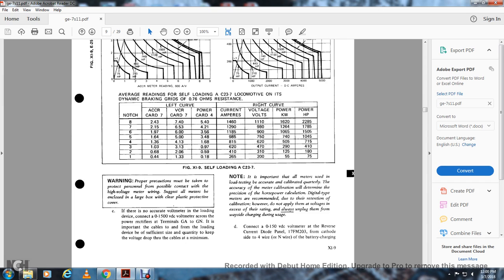This is an important cable to size with sufficient quantity from the loading of the device, to keep the voltage drop of the cables to a minimum. Note it's important that all the meters used in the load testing are accurate and calibrated. The meter calibration will determine the precision of the horsepower calculation. Digital type meters are recommended to retain the calibration.